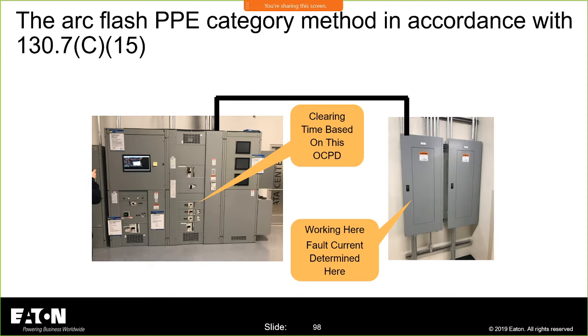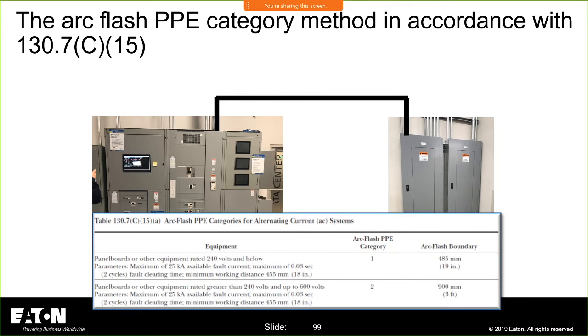So if I'm working over here on this panel board, I'm going to walk upstream and I'm going to look for the handles. If the overcurrent device that is feeding me has a handle, I know I'm in a molded case circuit breaker. If it doesn't have a handle, if it has those push buttons, because power breakers and insulated case circuit breakers have a charging arm, we saw that earlier, and they have a push button to turn it on and off. They don't have a handle. Right. So now I know, okay, say this is a 480 volt panel, so that's 480 volts. I am into this second row. I'm in PPE category 2, as long as I estimate the length of the conductor.